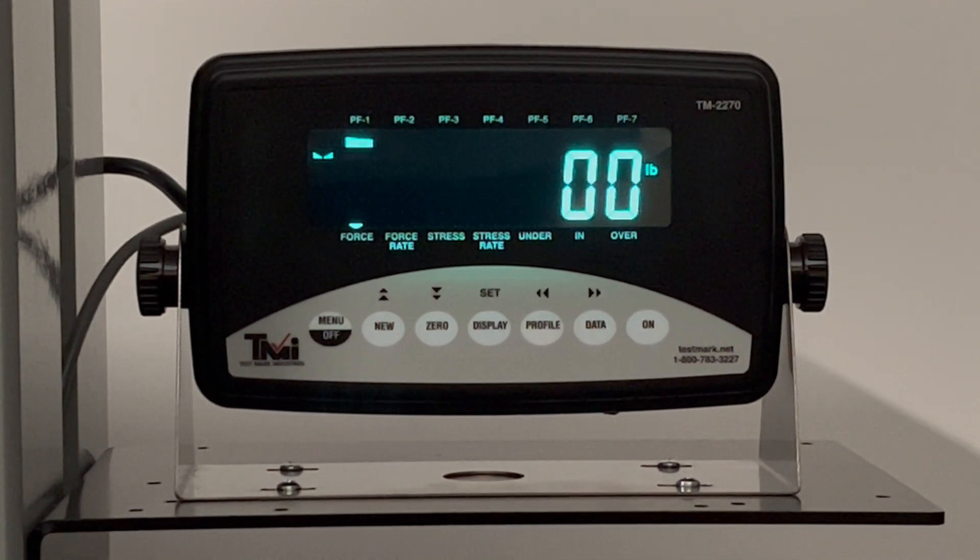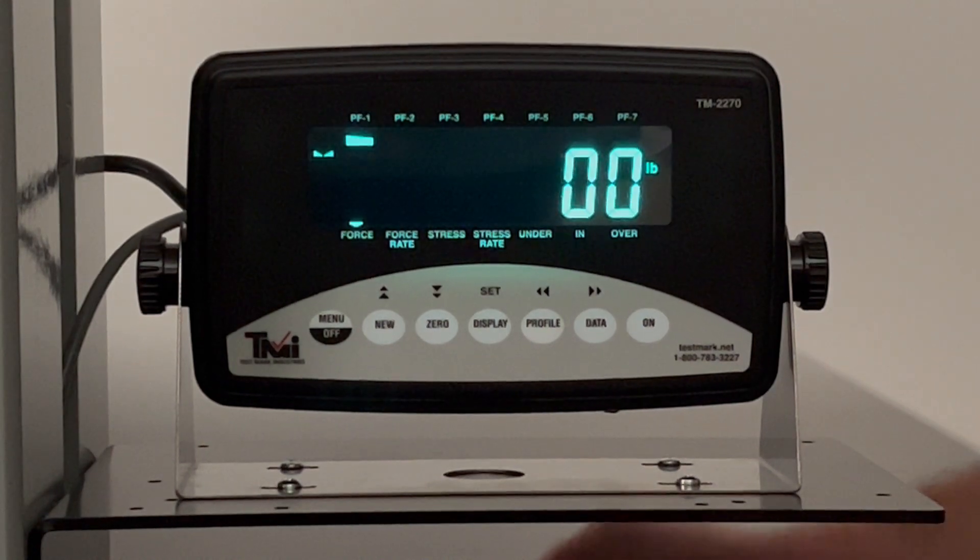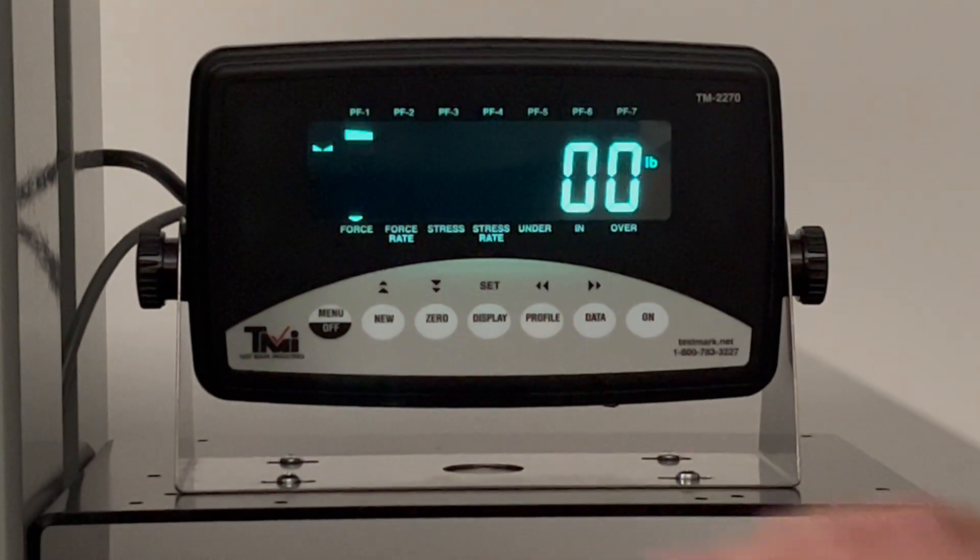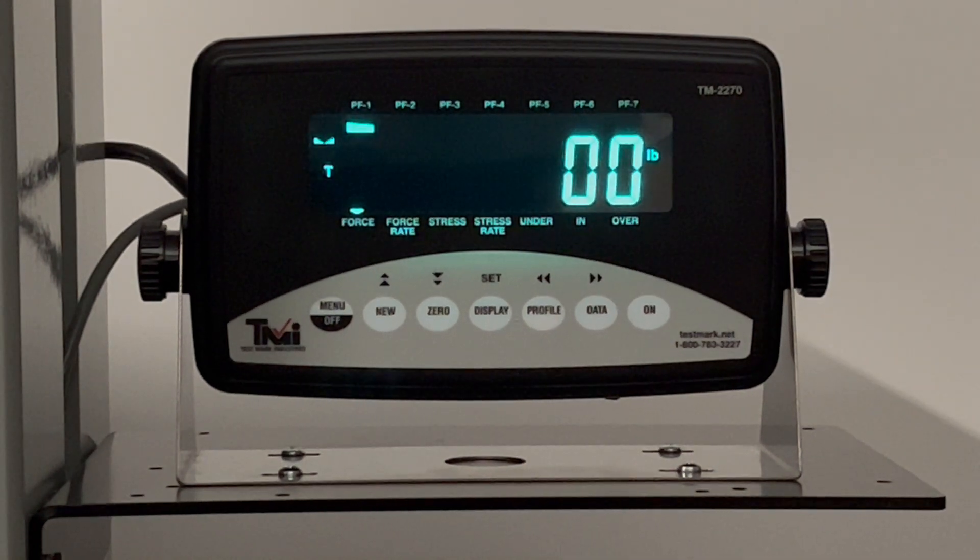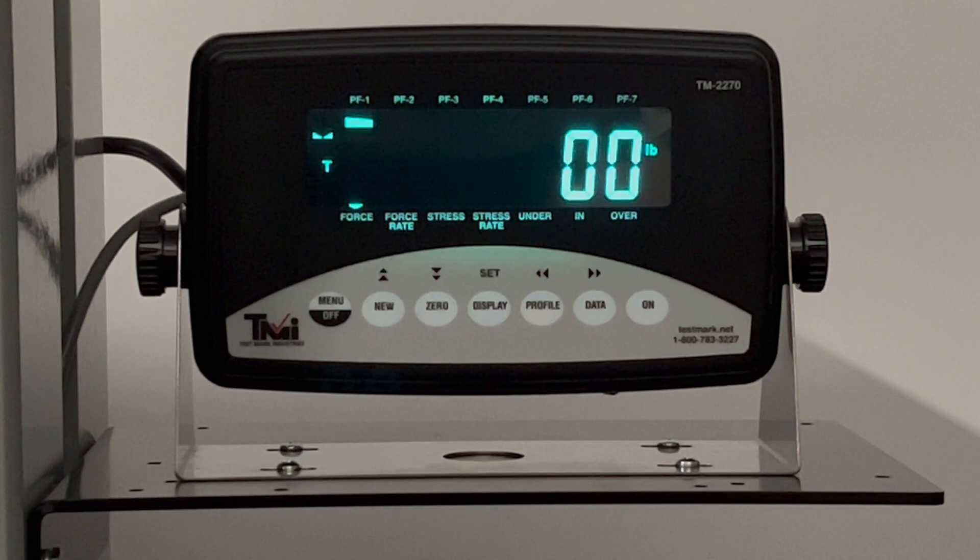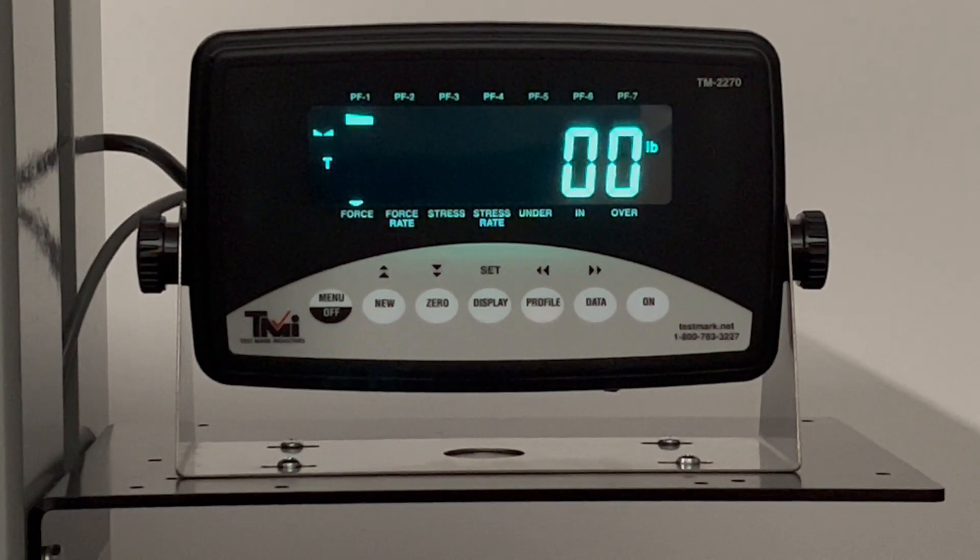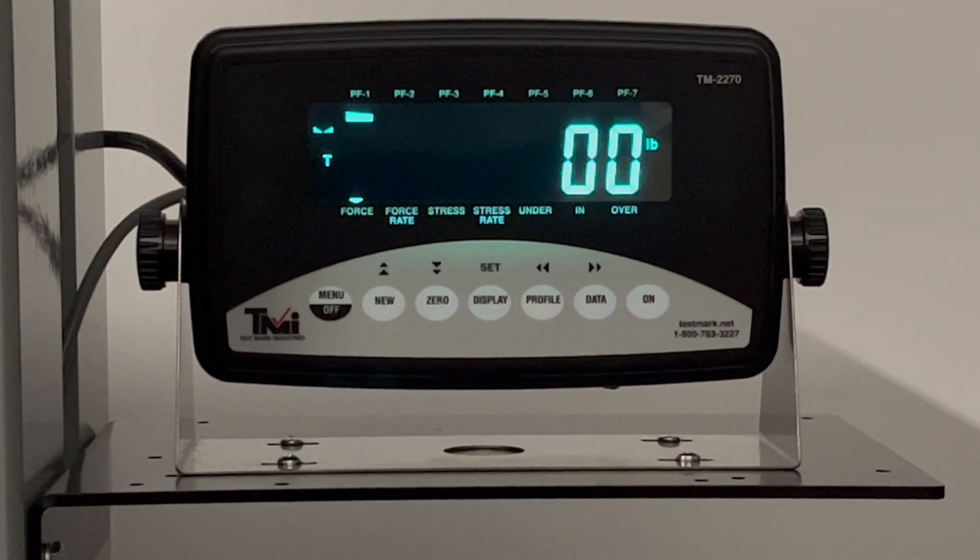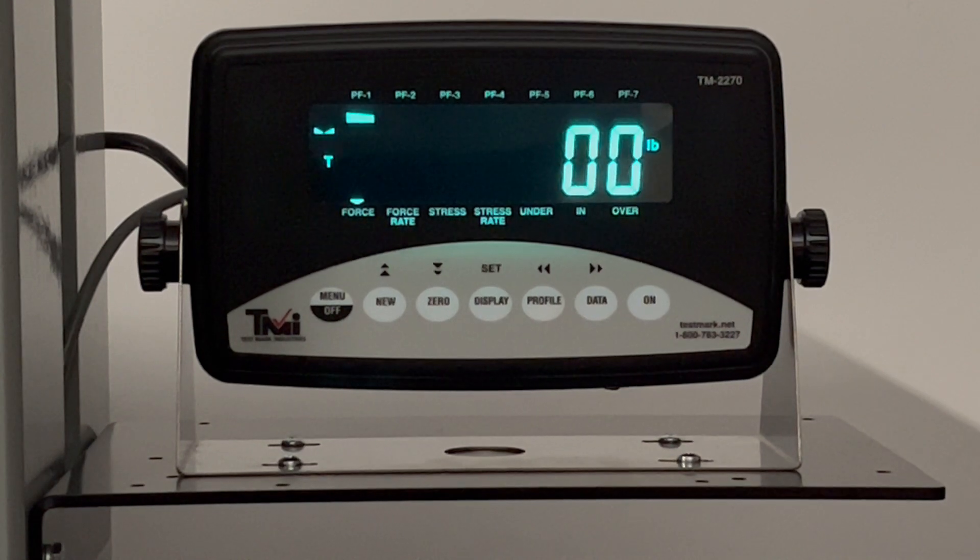To begin this test, I will turn the pump on and I will press the new button. You will see a T appear on the screen to let the operator know the test has begun. The screen will also change color to let the operator know once they have passed the load threshold.